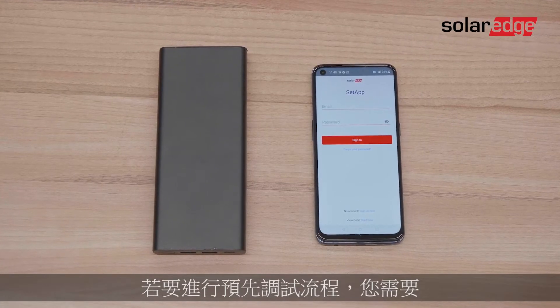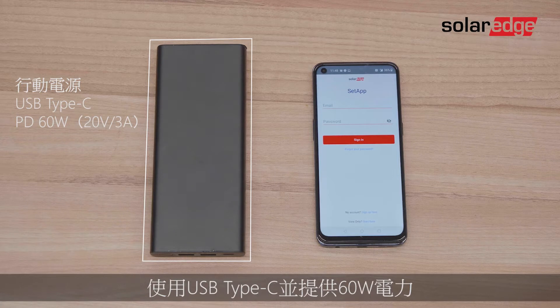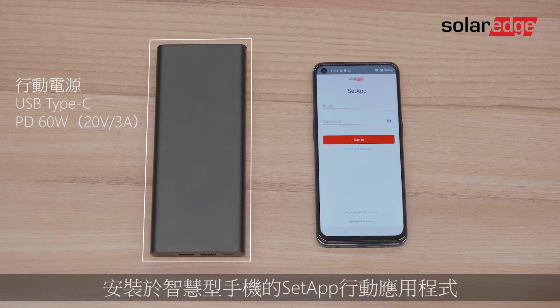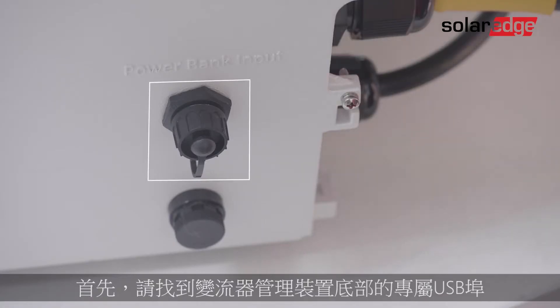To perform the pre-commissioning flow, you'll need a fully charged power bank with USB Type-C and 60 watts power delivery, outputting 3 amps at 20 volts, and the SetApp mobile application installed on your smartphone.